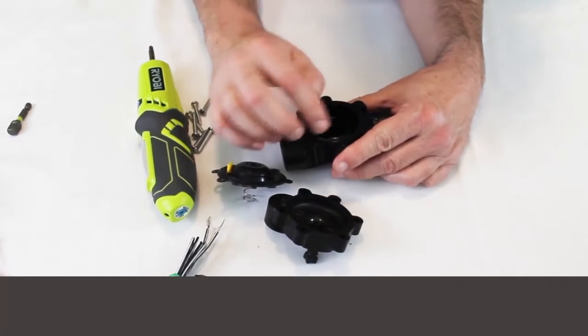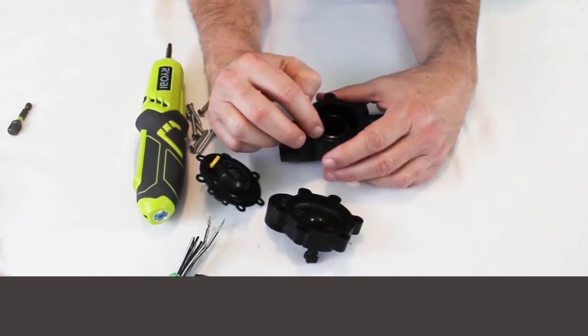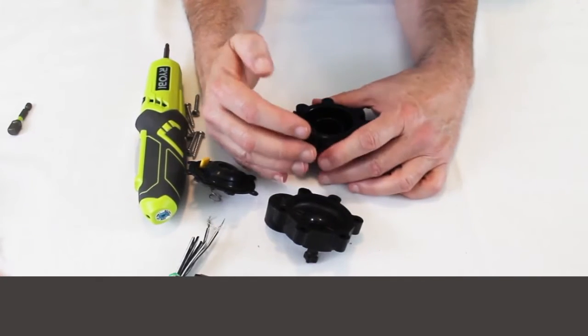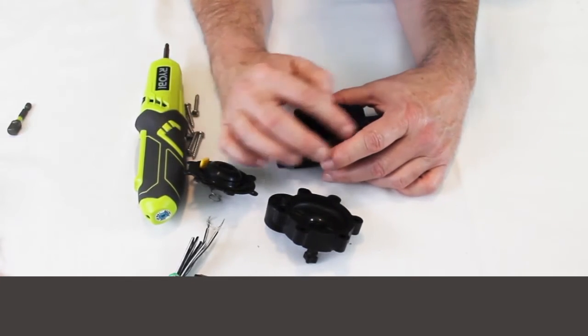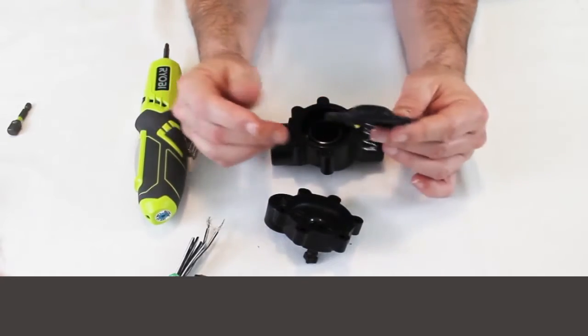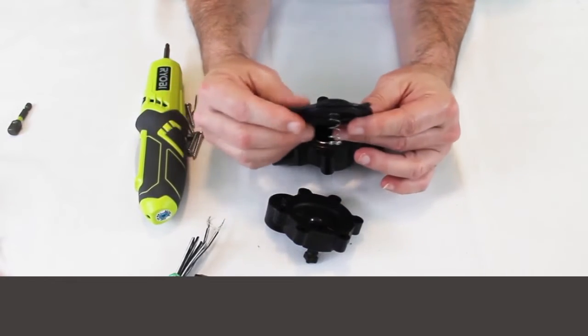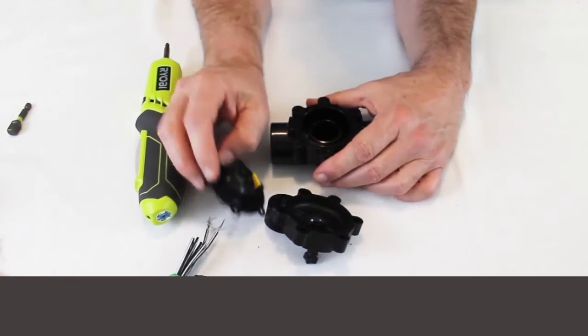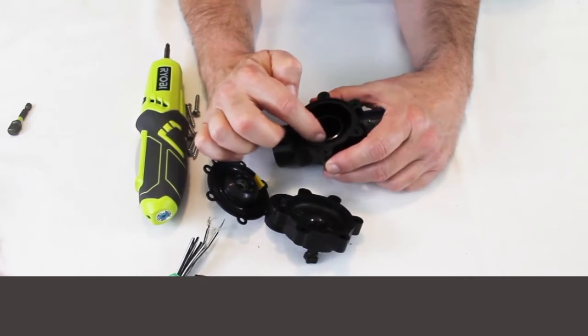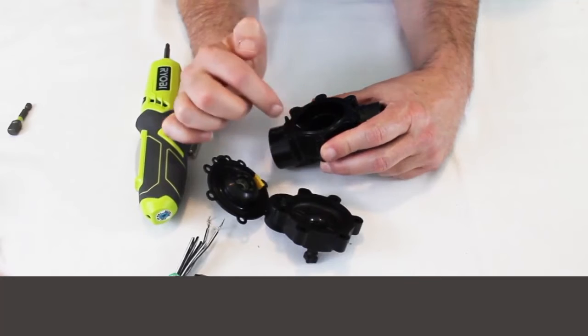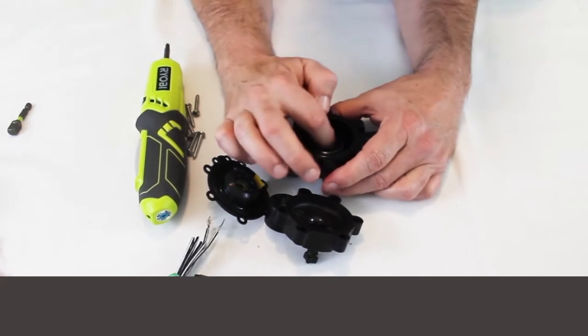Just check it, clean this out. I always usually have a cup of water and a toothbrush on hand to clean this out. If you're doing this in the field in a dirty situation, you're always going to get a little bit of dirt back on here. So when I get ready to put it back together, I always flush this out, wash off the diaphragm if I'm putting the original, and even if I'm putting new parts in there, I make sure I wash everything off and make sure there's no little pieces of plastic or anything that might hold this open or cause a leak. We're going to check down inside here and make sure there's no debris or gravel or anything there, chunks of PVC that's down inside of here. You can stick your finger down in there and just make sure that there's nothing that's causing the problem.